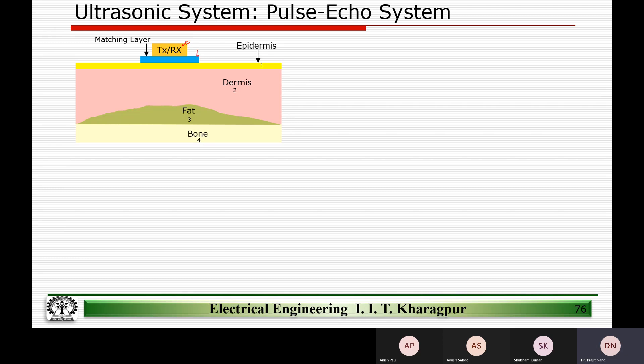We talked about the matching layer and why it is important — what should be the acoustic impedance of the matching layer in correspondence to the characteristics of the transmitter and the next medium. We derived a relation between that. Typically this can be PVDF material or a gel that can be put. Then we have the skin, epidermis, dermis, fat, and bone — this is the cross-section of the body.